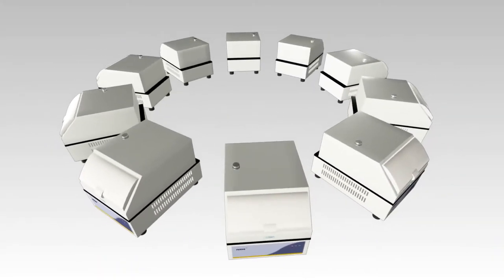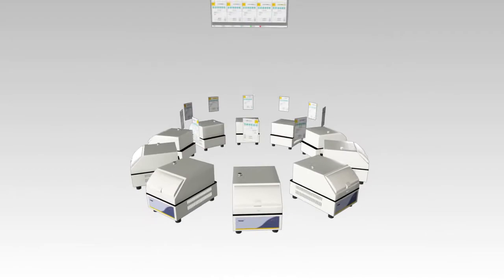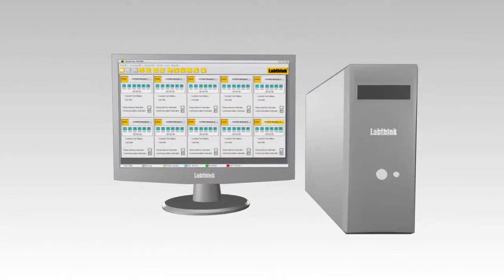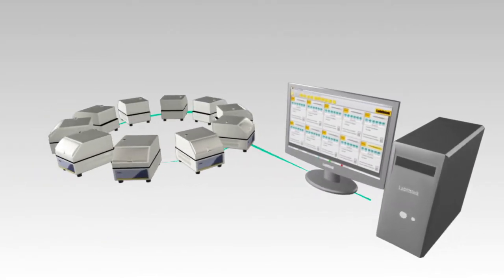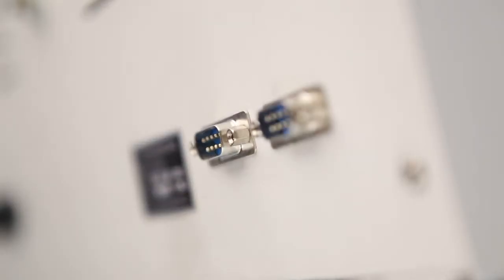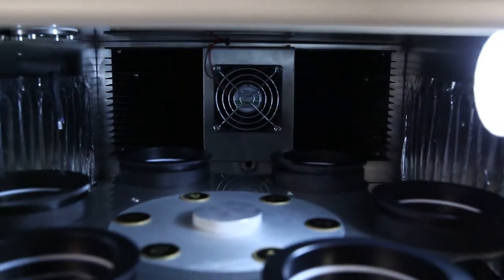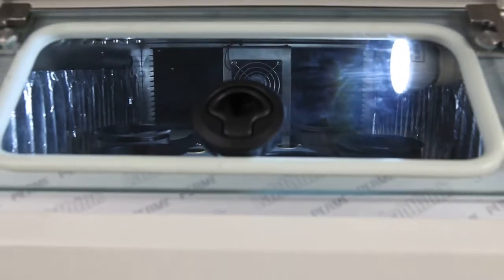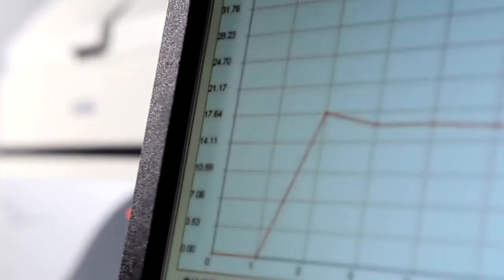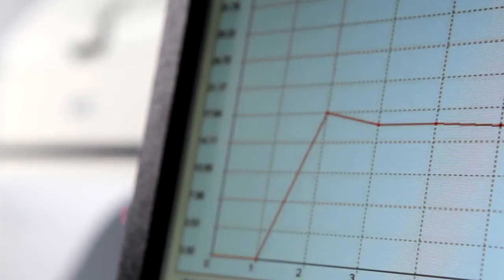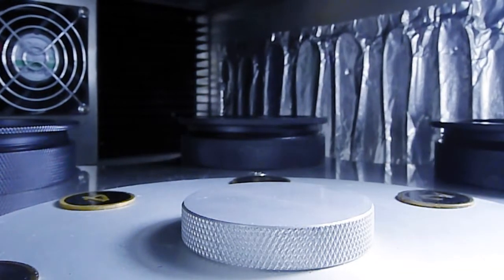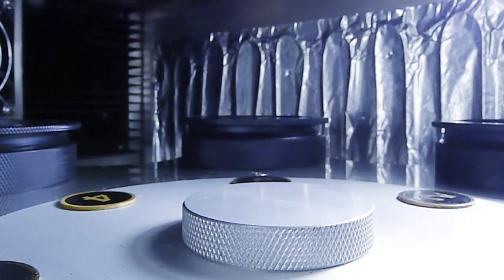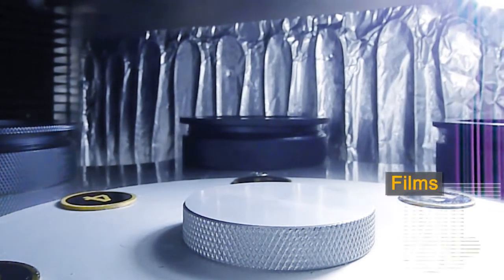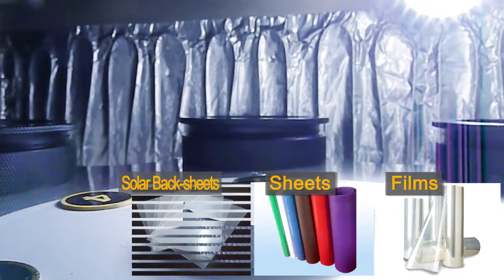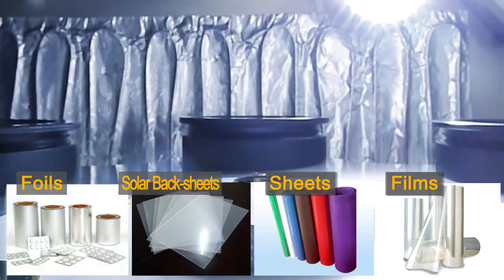One master base can be easily connected to a maximum of 9 satellite modules to accomplish up to 60 independent tests at the same time. It provides research institutions and manufacturers with an excellent solution for conducting multiple sample testing and significantly reduces the parameter setting time and test duration. This instrument can be used for WVTR tests of flat materials such as films, sheets, solar back sheets, foils, and others.